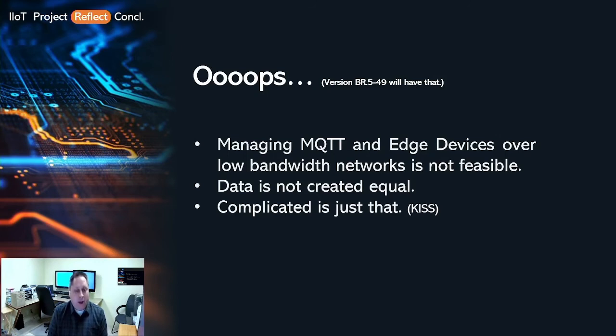So the main thing about edge processing is that you are adding complexity to a system that is relatively simple as it is now. You go in, you set up your comm stations, you've got your tags, you start polling, you're done. That was a drawback in our world because it's a learning curve. Number one, you're learning a very broad spectrum of devices, hardware, and all of those kinds of things. But you're also adding to the complexity of the maintenance and configuration that goes with it. It's almost 2 to 3 times more complicated than it was under the previous polling mechanisms. So those were some of the drawbacks.